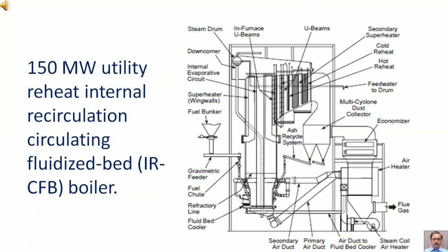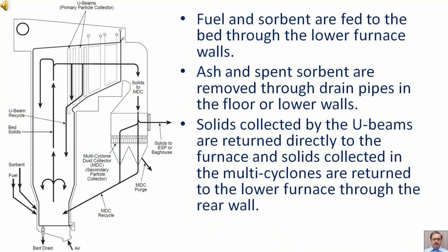In the diagram, 150 megawatt utility reheat internal recirculation circulating fluidized bed boiler is shown. Fuel and sorbent are fed to the bed through the lower furnace walls. Ash and spent sorbent are removed through drain pipes in the floor or lower walls. Solids collected by the U-beams are returned directly to the furnace and solids collected in the multi-cyclones are returned to the lower furnace through the rear wall.